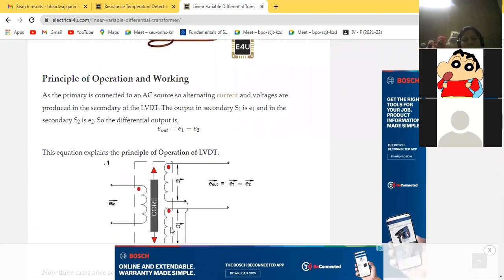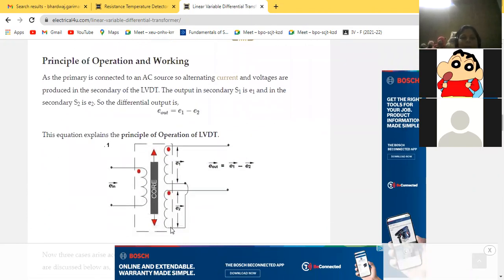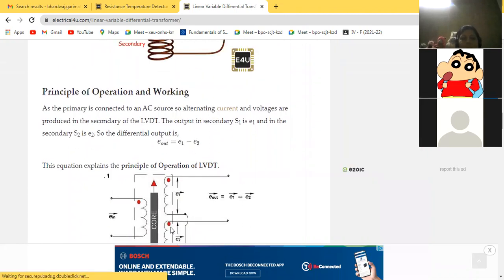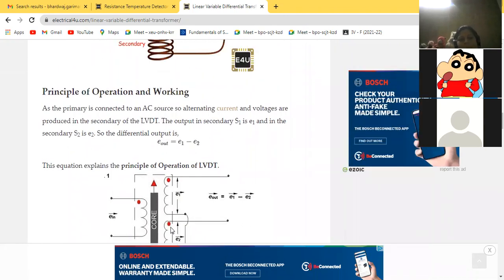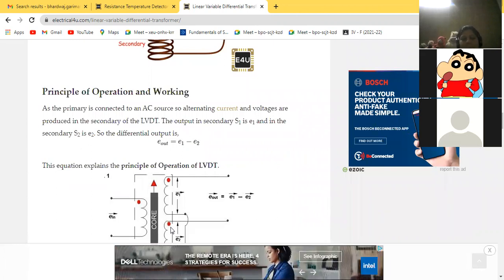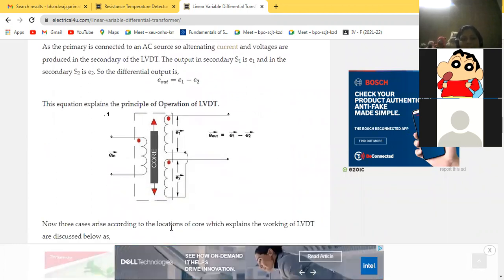Now the principle of operation and working. As the primary is connected to an AC source, alternating current and voltages are produced in the secondary of the LVDT. The output in secondary S1 is E1 and in secondary S2 is E2. So the differential output is Eout equal to E1 minus E2. Now this equation explains the principle of operation of the LVDT. You can see here Eout is equal to E1 minus E2.